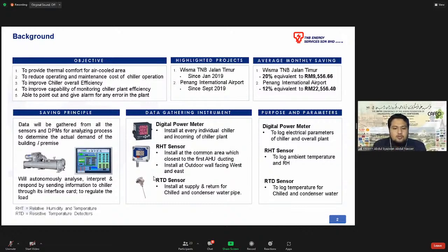Next we'll be using RTD sensors, resistive temperature detectors. These will log the temperature for chilled water and condenser water, both supply and return. All the data will be analyzed and interpreted, and the brain will instruct the chiller to supply a suitable chilled water temperature.